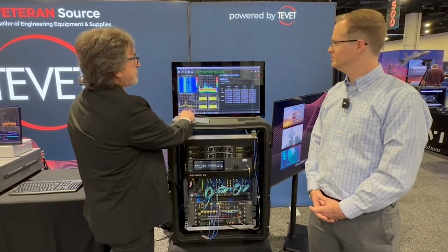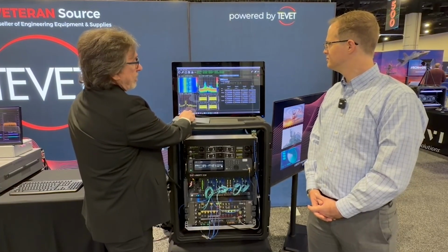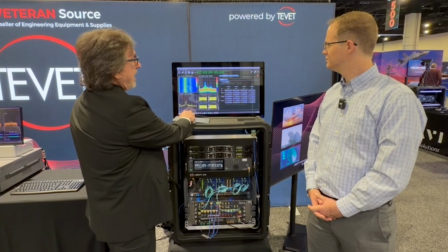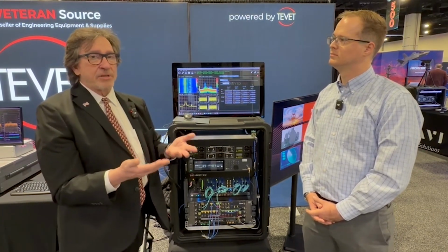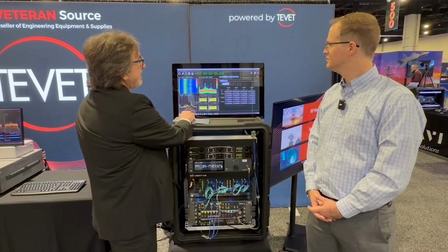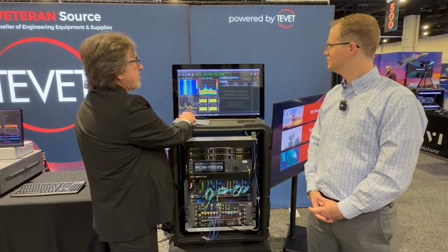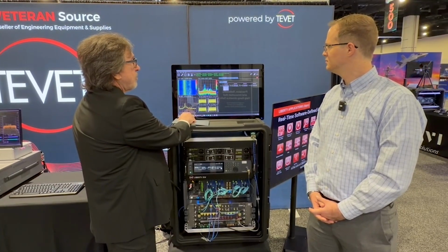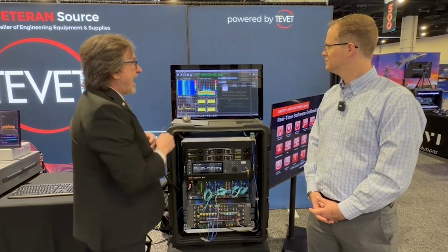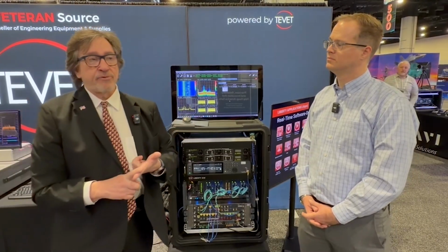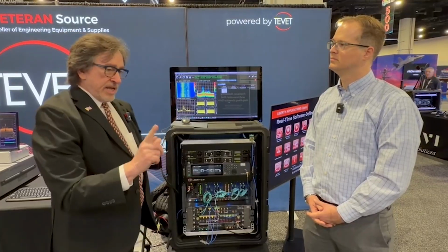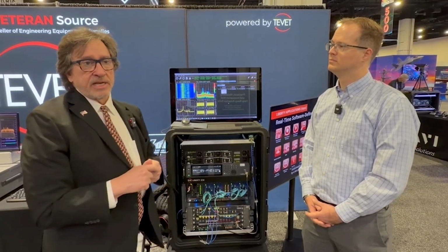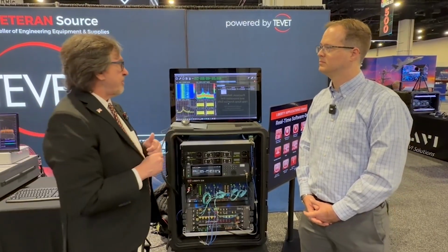From a triggering perspective, when you set up mode, it'll ask, do you want to do snapshot mode or contiguous mode? So you have the ability to control that. If I go to the trigger, here I can select the trigger for each one of the channels. What we have are, you can do free run. Free run means that's a software keystroke. You set this up and you just hit a key and it'll start the recording process.